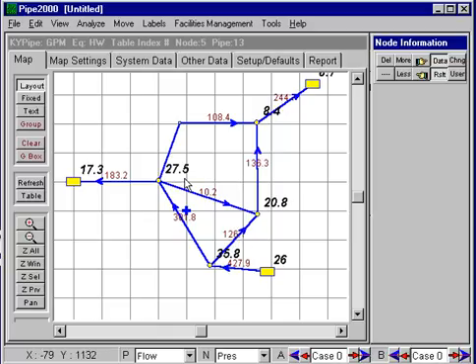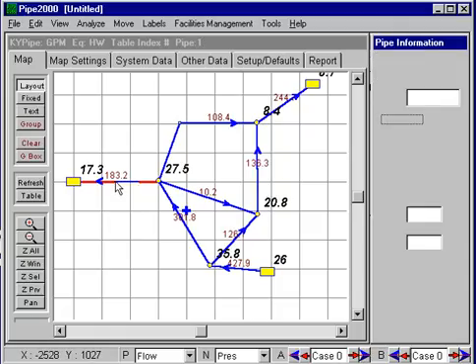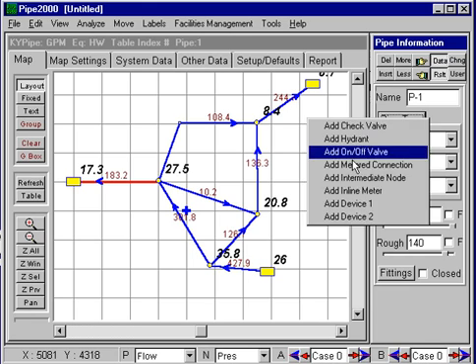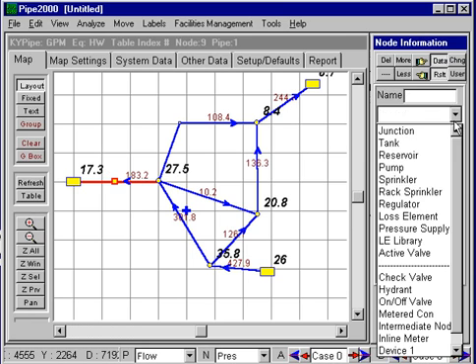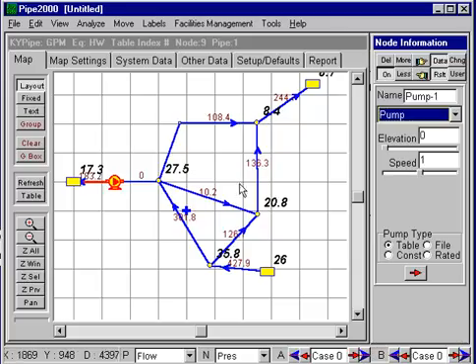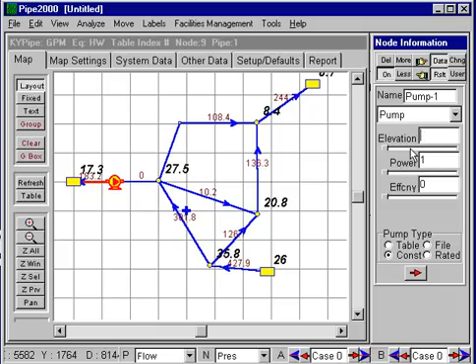Let me quickly add a pump here just to see what happens. So I'll select this and insert an intermediate node, then change that intermediate node to a pump. The pump is going in this direction, and I'll put in a constant power pump — the elevation we know is around 200 feet. Let's put in a power of 50 horsepower, and we can now run the analysis.